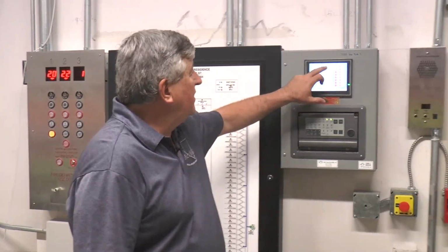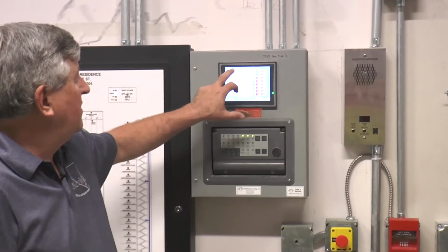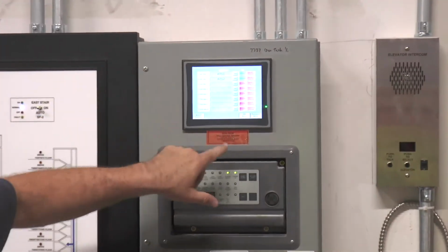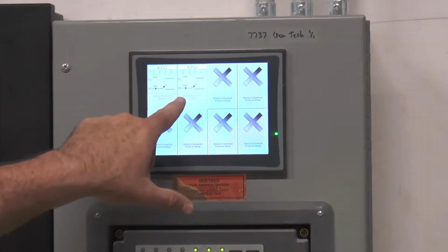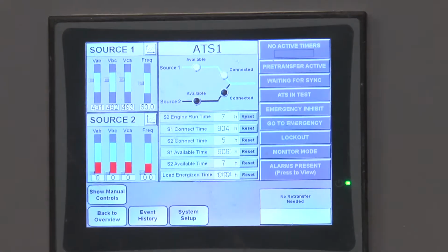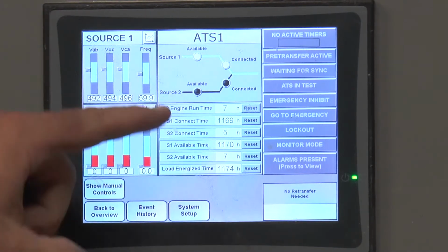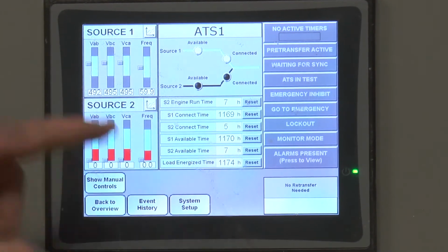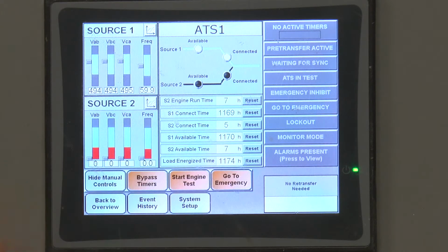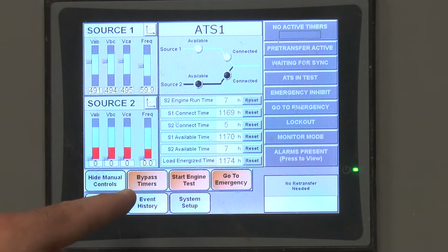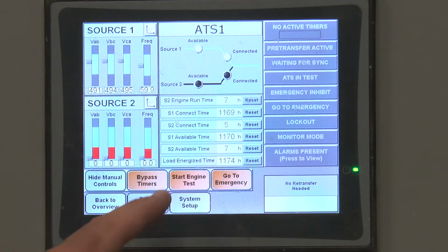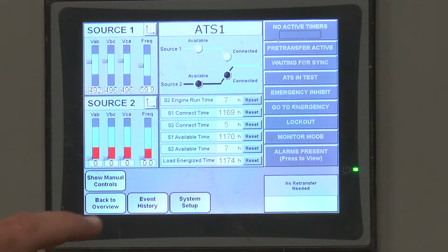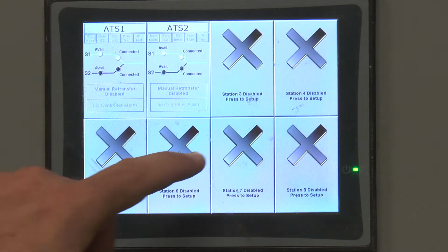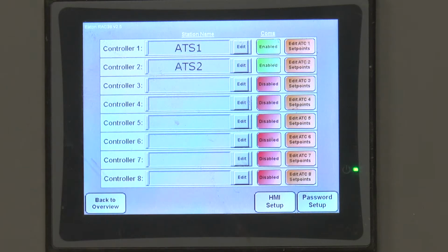Transfer switch control, you touch the screen, oops. Let's see, you see a touch screen that gives you the position graphically of exactly what the transfer switches are doing. You hit that, and it gives you your voltage, position, and your run hours on that transfer switch, so you know the condition. The transfer switch also has the ability to manually start the generator set here for fire command, run the generator, and also go to emergency if they so choose during an event. To hide those controls, just go back there to get back and go back to the main screen, and that's it for the display.